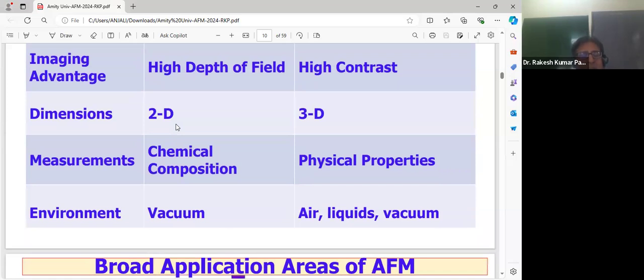As you know, the scanning electron microscope requires vacuum, a high order of vacuum. That is what the scanning environment should be. In fact, you can say this is the drawback of the electron microscope. It requires a high order of vacuum. And most of the time the instrument system goes out of order because of this high order of vacuum. Whereas there is a facility in case of AFM that you can perform this raster scanning in air, liquids or vacuum. The option is there. So because of this option, we prefer to go for AFM rather than SEM.